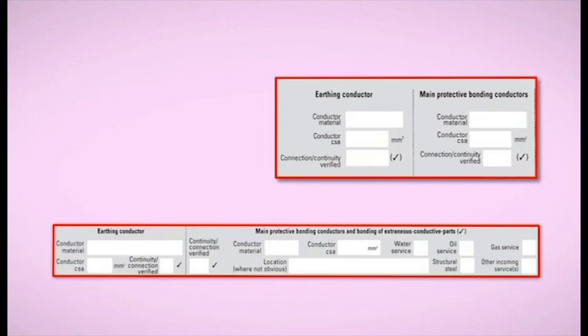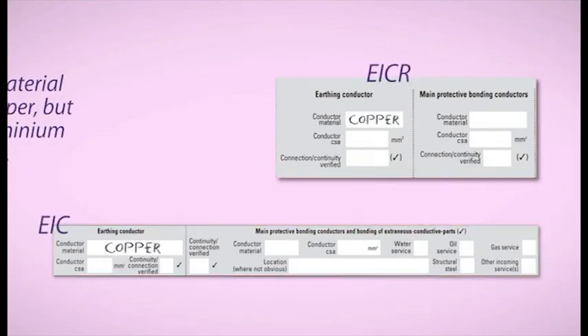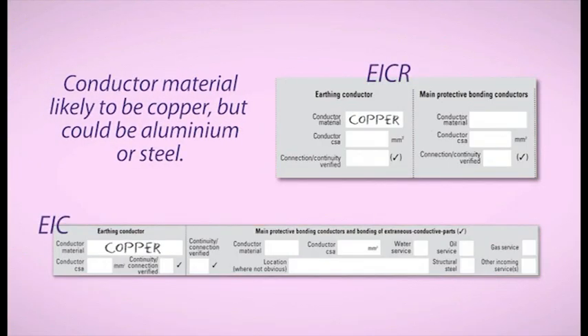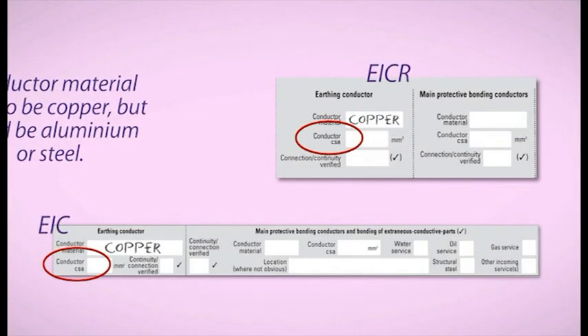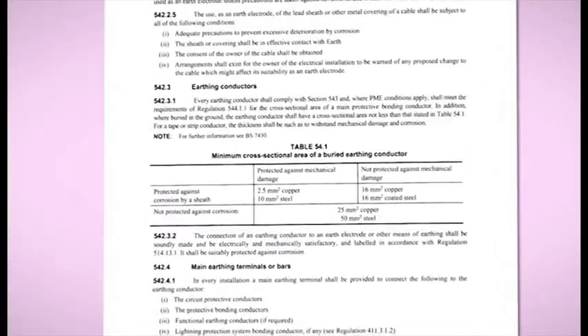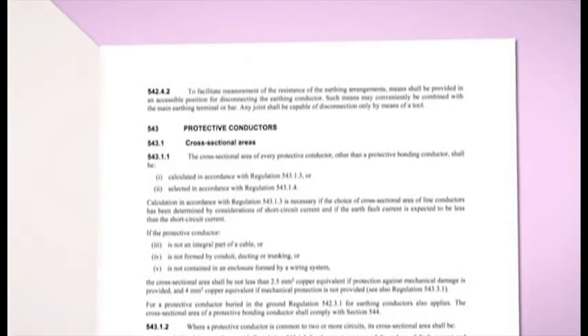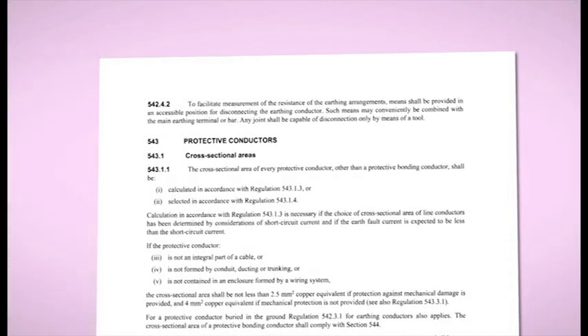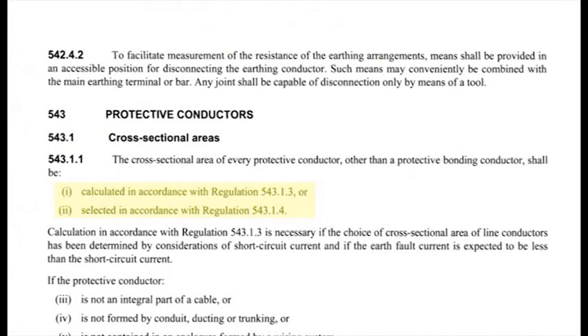Next, let's look at boxes referring to protective conductors. First, we have the earthing conductor. The conductor material will generally be copper, but it could be aluminium or steel, and the cross-section area needs to comply with the requirements of Regulation Group 542.3 and Section 543. Here you will find detailed information on how you can either select a suitable cross-section area or calculate it.